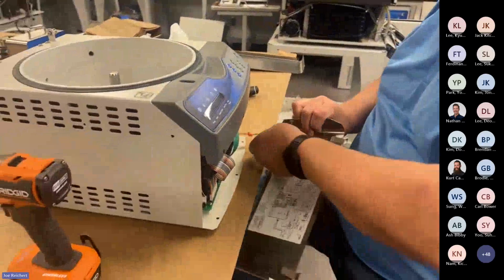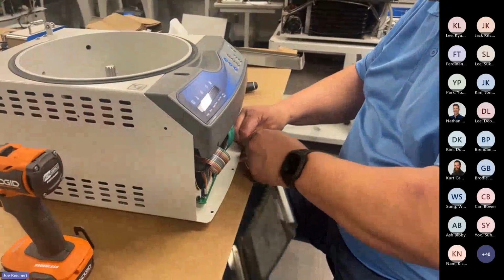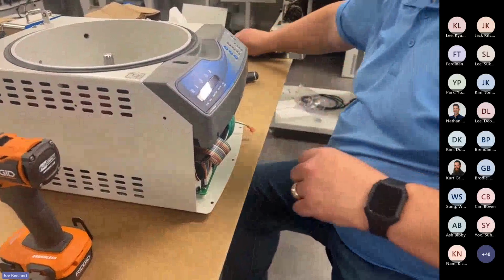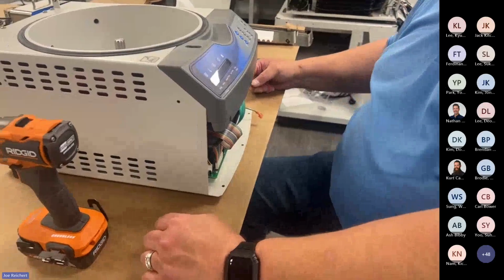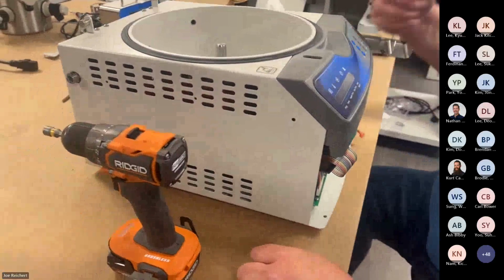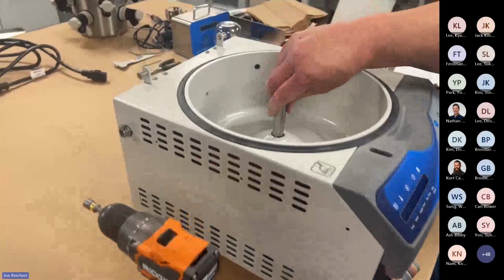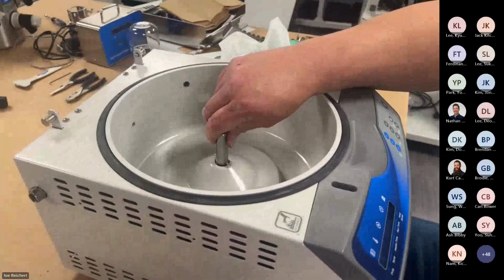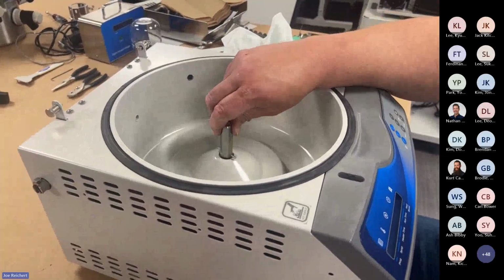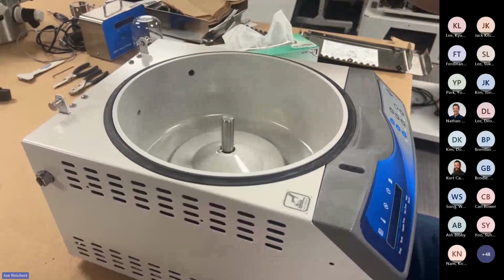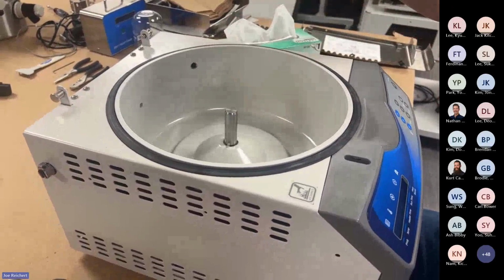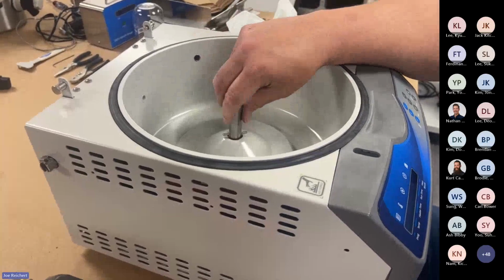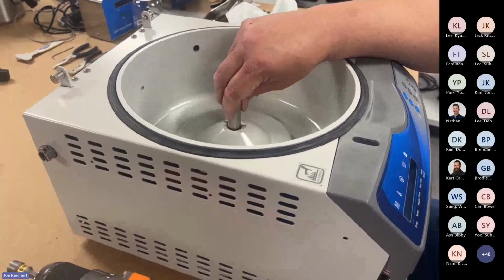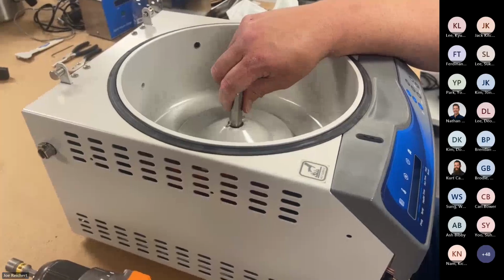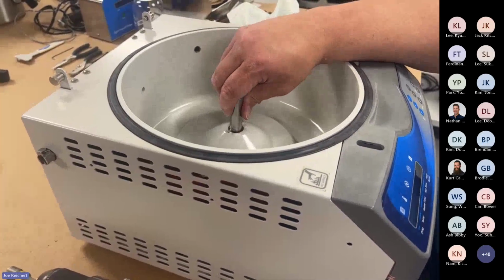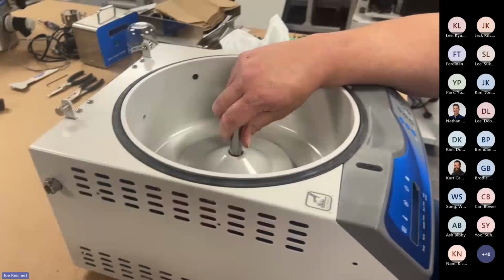I do get customers that want to buy a new motor because it says motor error, and I'll tell them that is not their problem. The problem is going to be the Hall effect sensor underneath. That's what measures the rotation, the RPMs of the shaft. It should be very free. I should be able to turn it and it just spins and spins without much issue at all. But if you're turning this slowly and you feel any sort of resistance or some crunchiness to it, heavy sounds, that is bad. There's something in there.